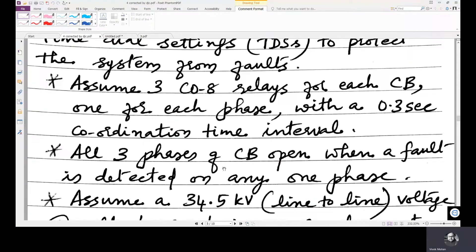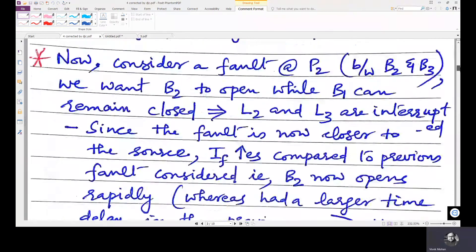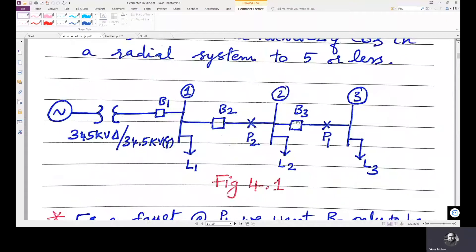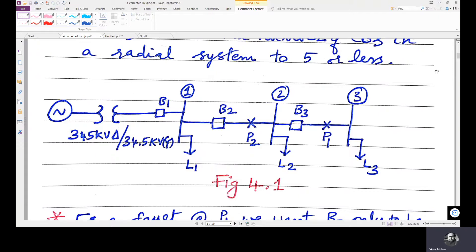Assume three CO8 relays for each circuit breaker, one for each phase, with a 0.3 second coordination time interval. The coordination time interval means: for a fault at B3, B3 is the primary protection device, and if B3 fails to act, then B2 should act after a 0.3 second time delay as backup protection. Similarly, if there is a fault at B2, B1 acts as backup protection, again with a 0.3 second time delay between B2 and B1.